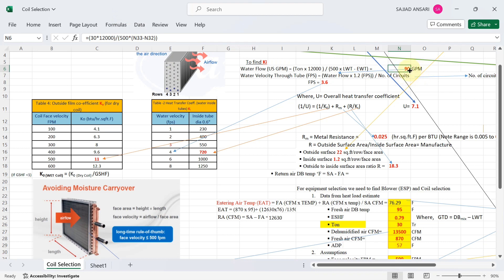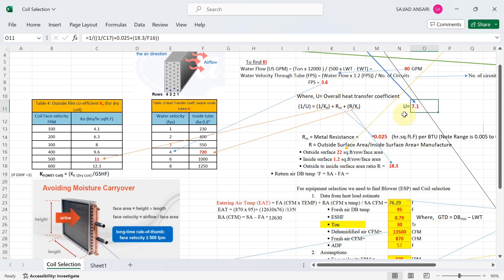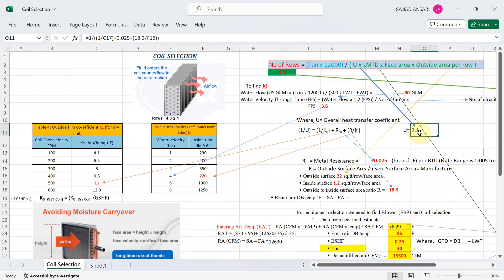Once you have the water flow of 90 GPM, put it into the velocity formula and you get a water velocity of 3.6 FPS. Referring to Table 2, 3.6 FPS is approximately 4 FPS, for which the heat transfer coefficient ki is 720. Putting all values into the formula gives an overall heat transfer coefficient U of 7.1.